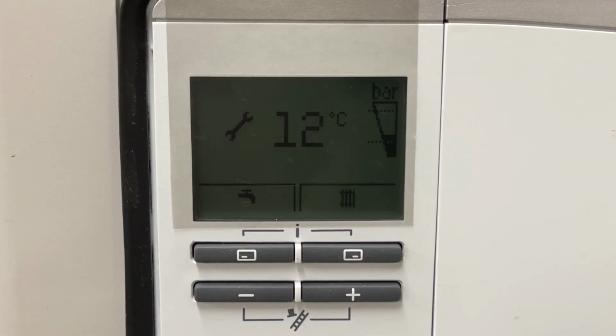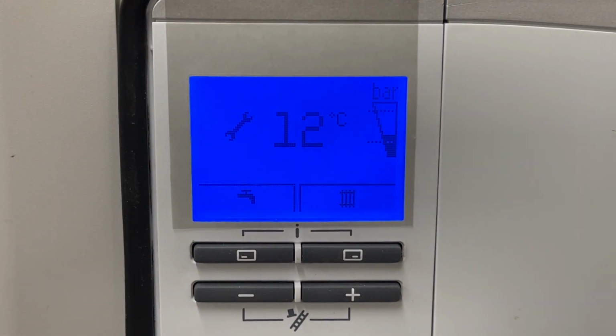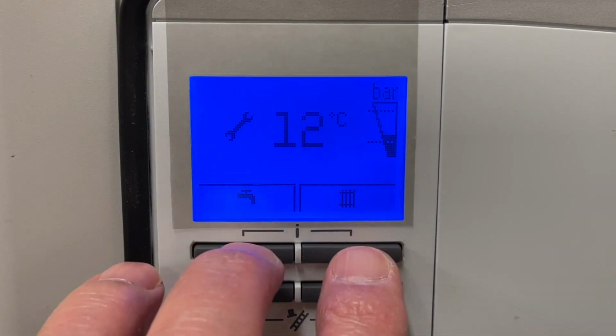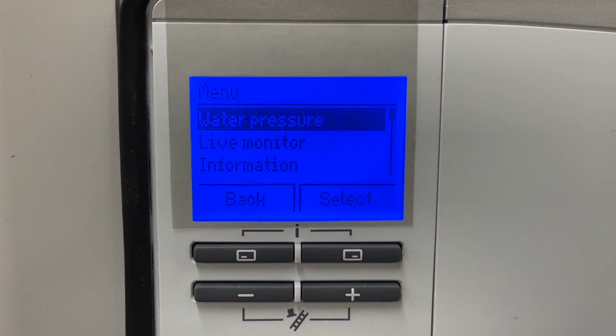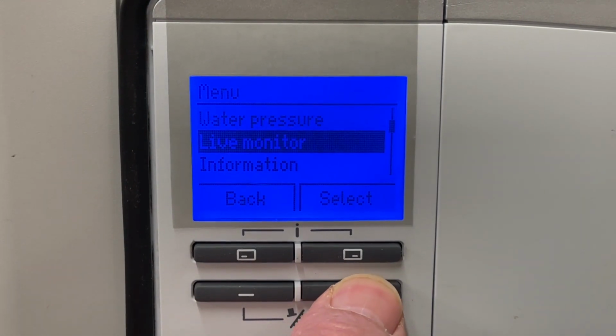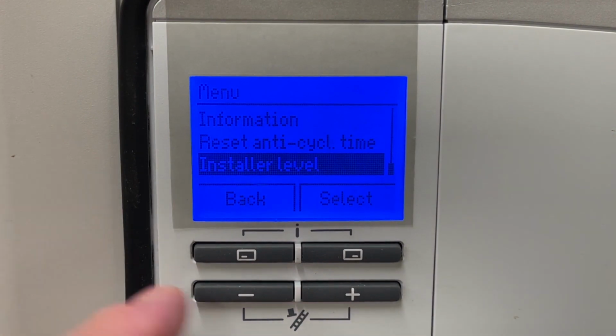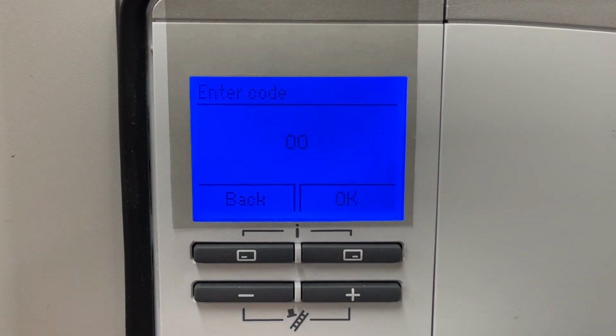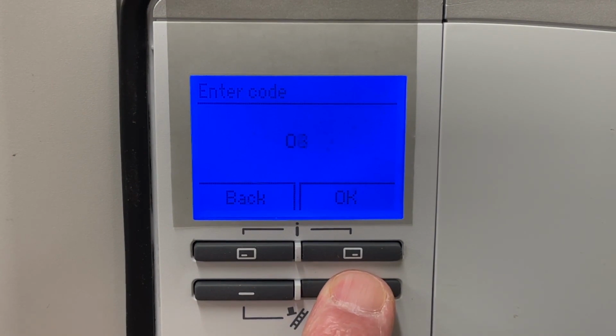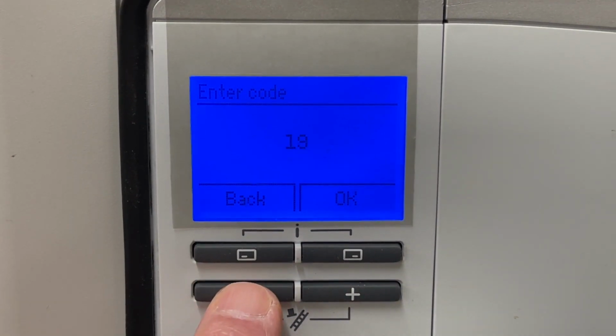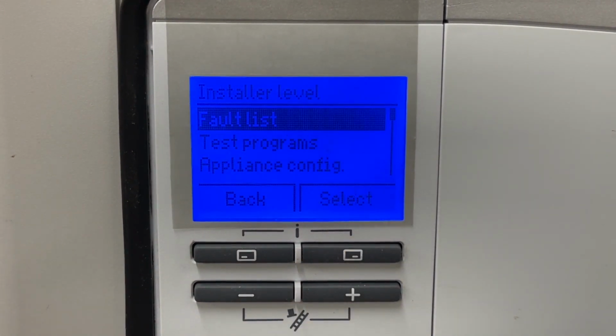To access the fault codes on the latest blue screen boilers, we simply have to press one of the four buttons to wake the screen up, press the two top ones for 1-2 seconds and release, and then with the plus button we're just going to go down to our usual installer level, which we are here, select, and now we have to change that by pressing the plus and go to number 17 as usual. So we just overshot a little bit, 17, we'll OK that, and immediately you can see we're in the fault code list. So now when we select this one, we will see the top 3 or the last 3, but it will go down to 10 as well.